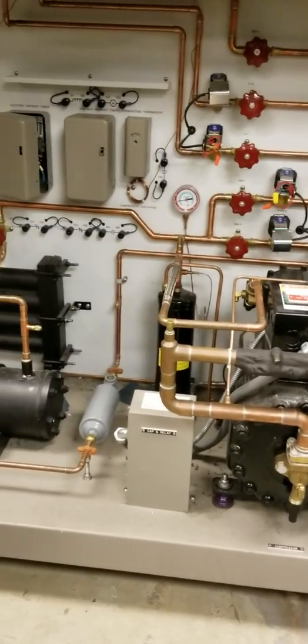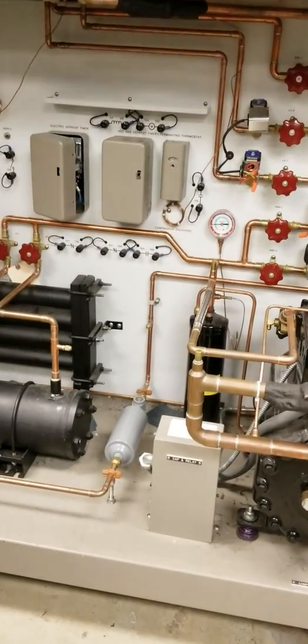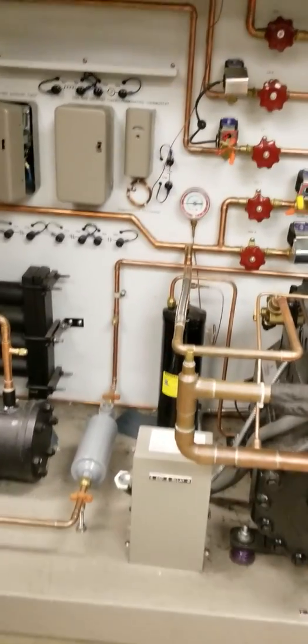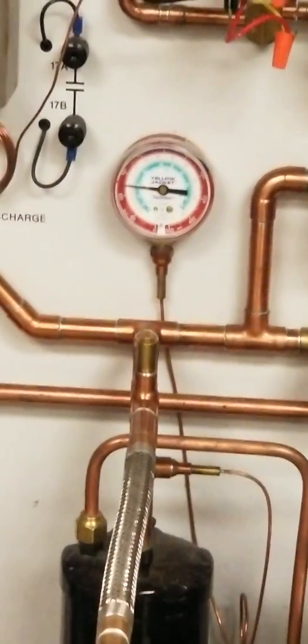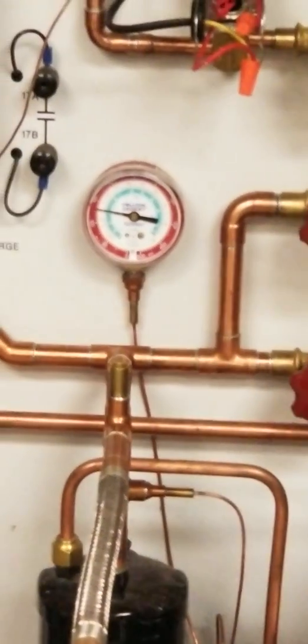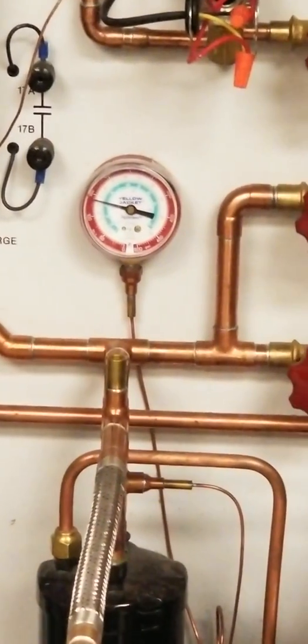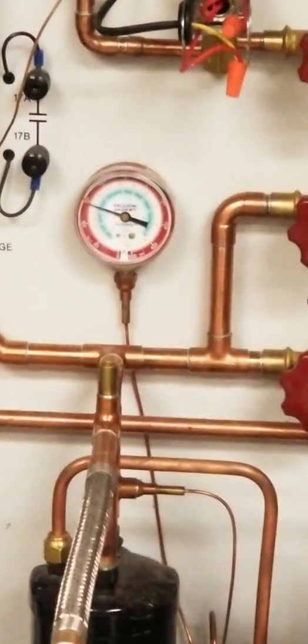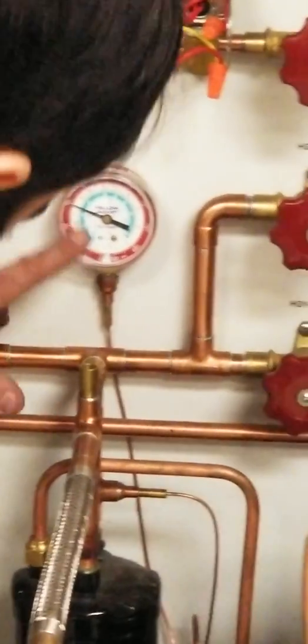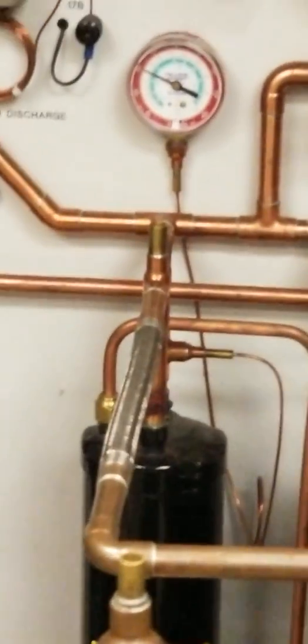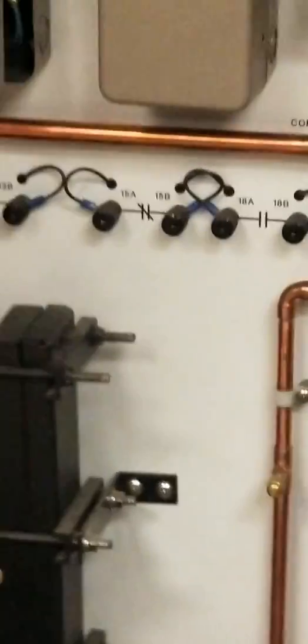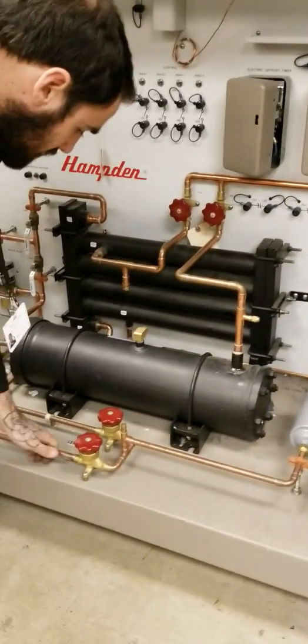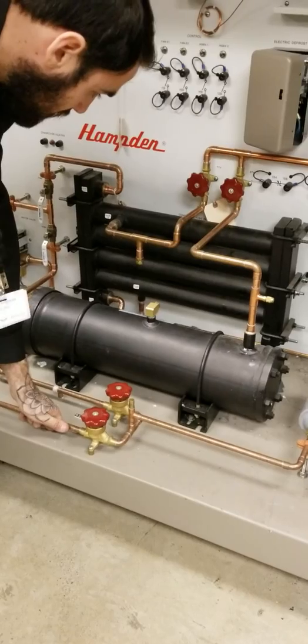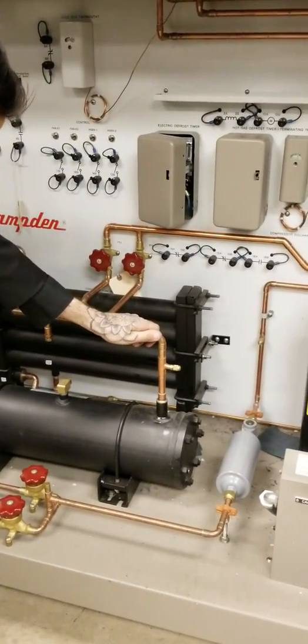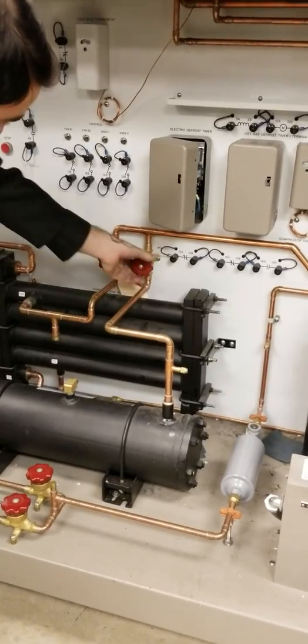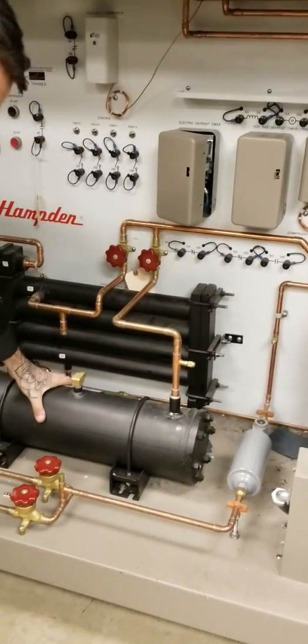What's not on? Our cooling tower. So our water pump is at our cooling tower. So we're not even circulating water through the pipes, let alone cooling down the water. So you just have standing water in the pipes that are about to start receiving heat. You can watch your head pressure. It's starting to build. You can feel the hot gas coming into the receiver and leaving as a hot gas still. The receiver is getting hot.